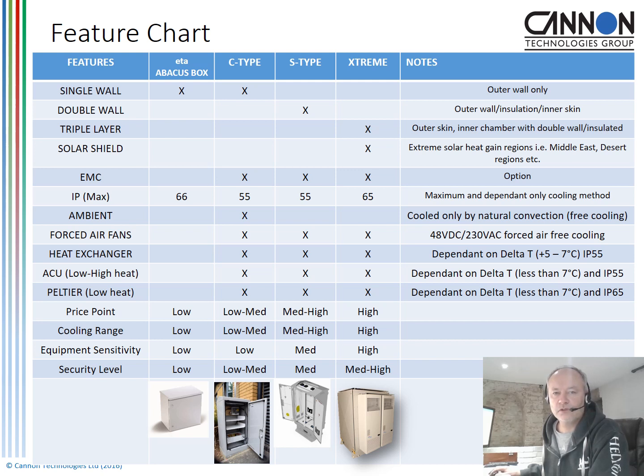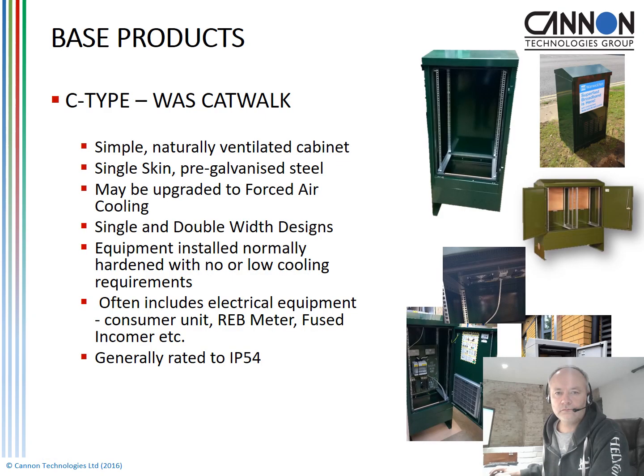We can provide up to an IP65 rating, and we use, as I've mentioned before, all of the different cooling mediums from ambient fans, forced air cooling, right through to Peltier devices. So you can see there, really Cannon covers the whole range, from the low right up to the high end of outdoor cabinet protection.